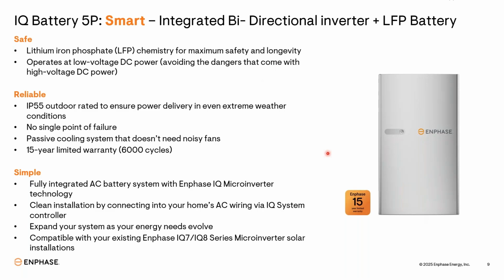So for DC current values, voltage is low and current is high. For that, you have to maintain the power there, and you have to increase your cross-sectional area. But here everything is AC. These batteries are AC coupled batteries, not DC coupled batteries. So whatever output you get from these batteries is AC only.